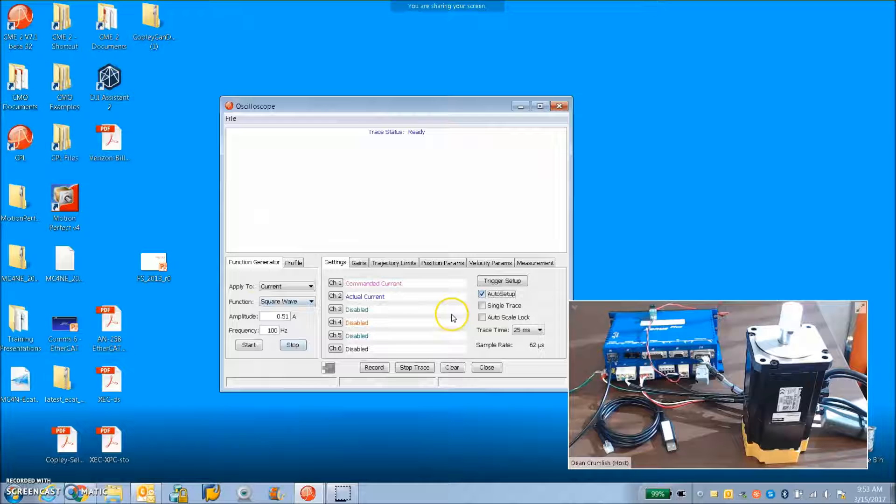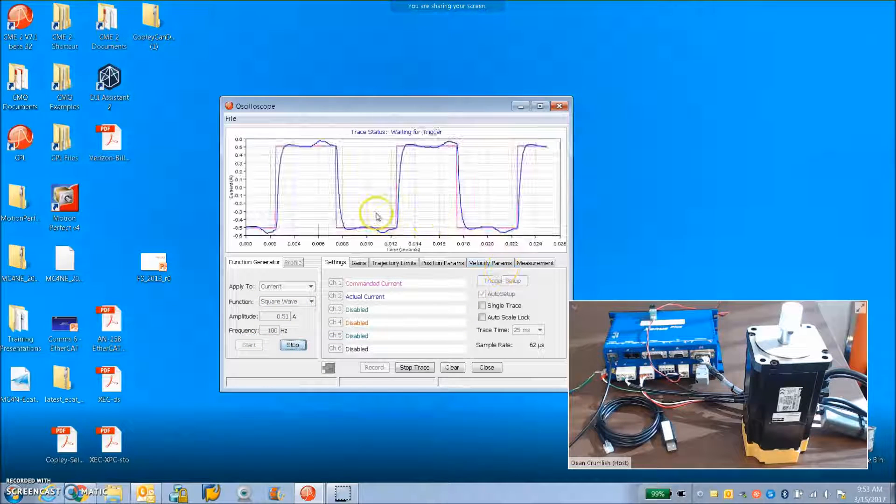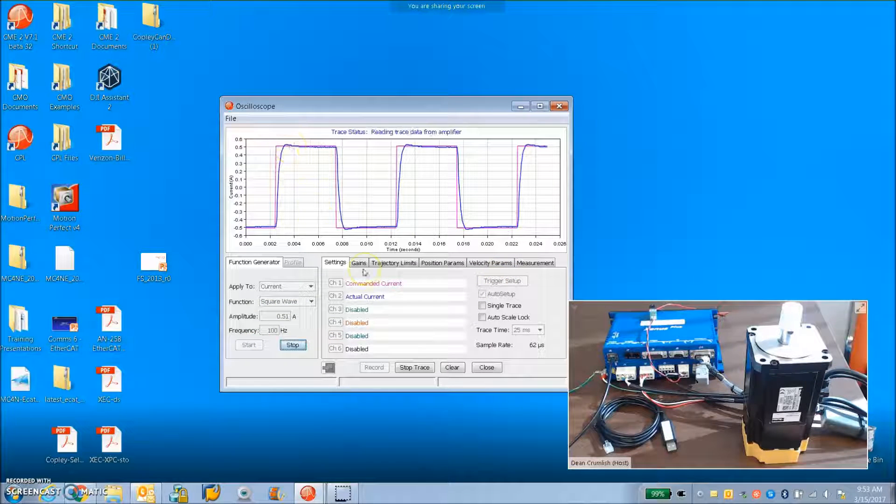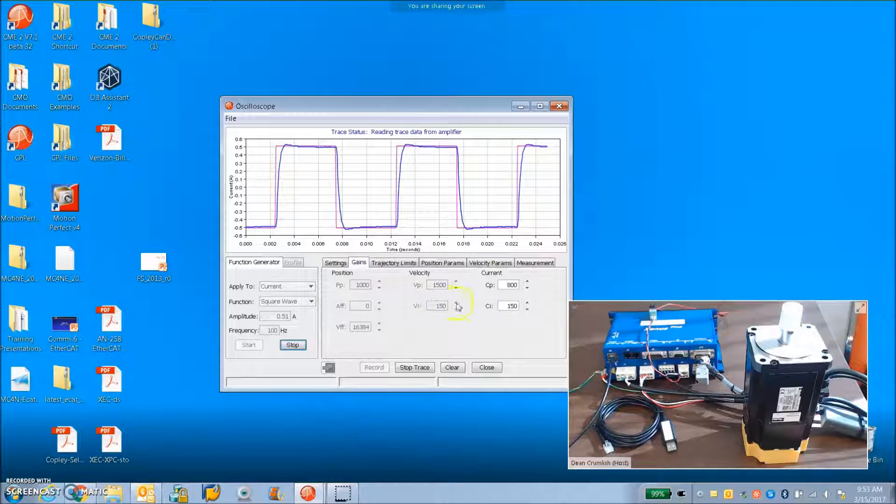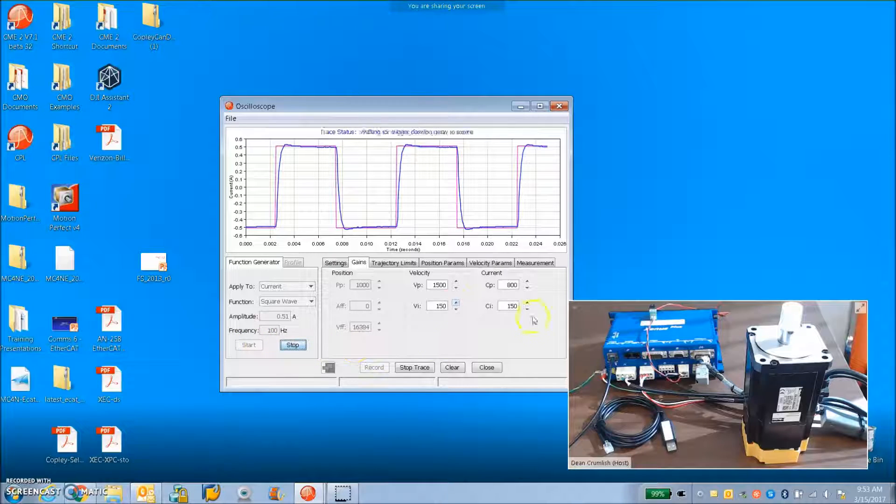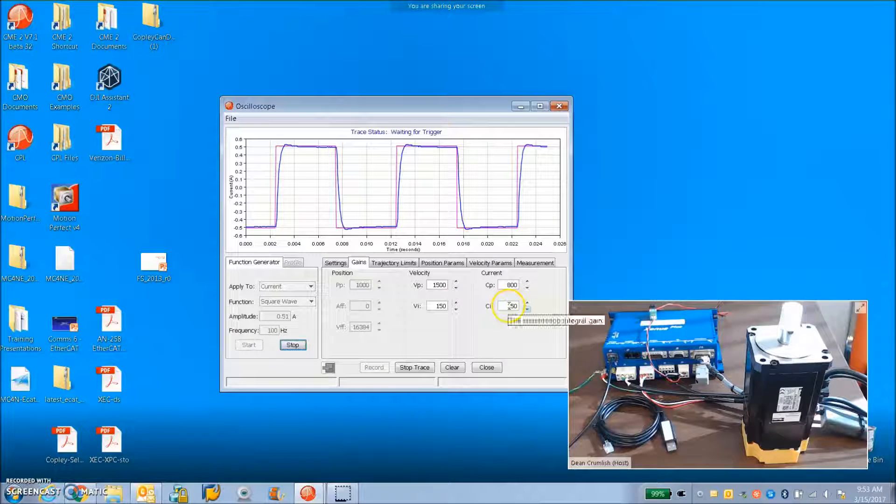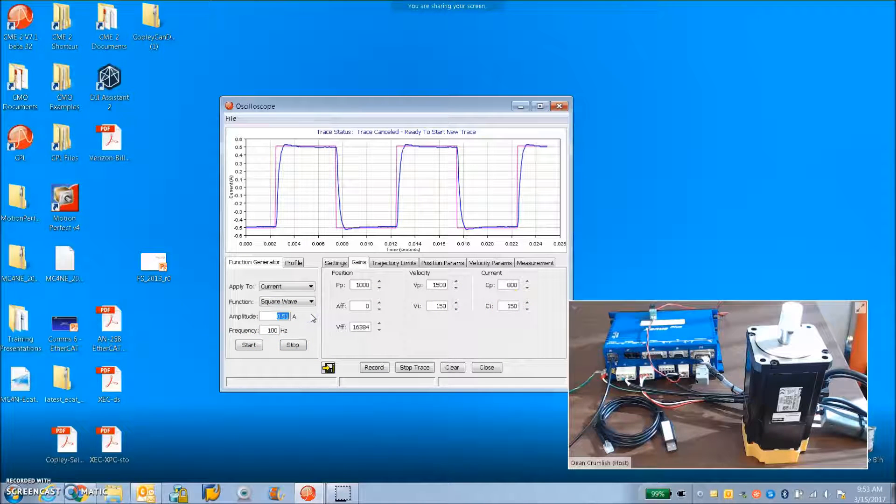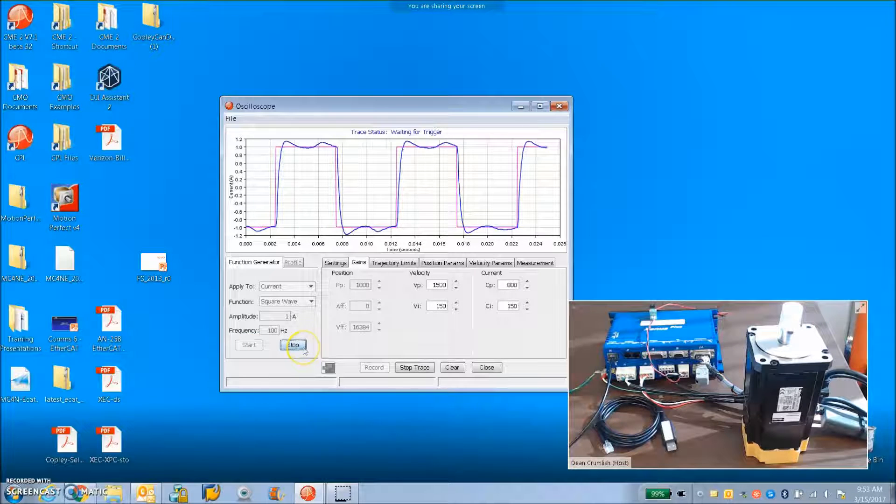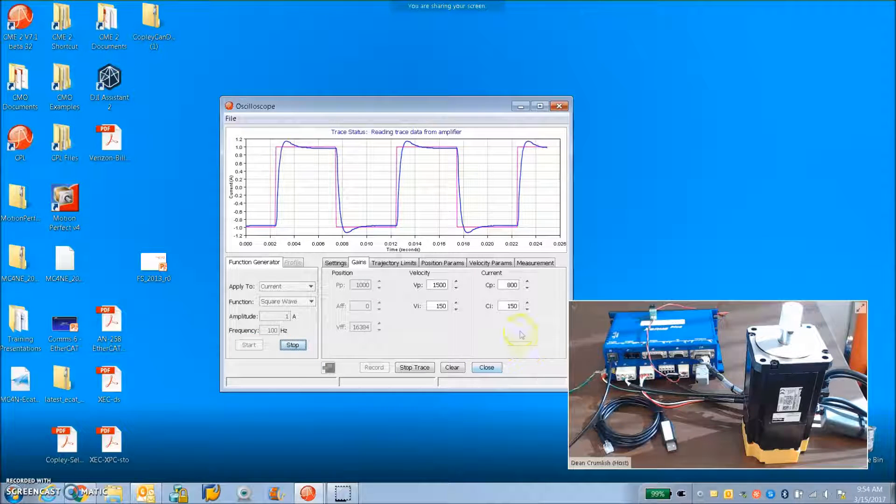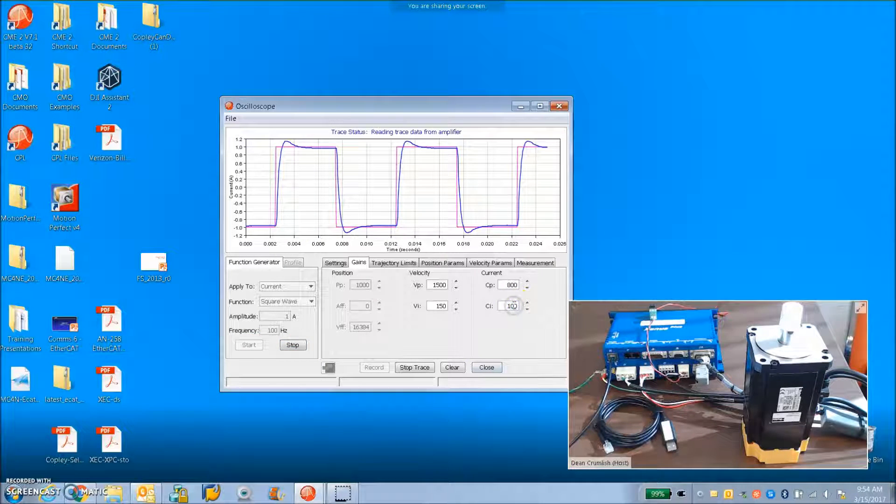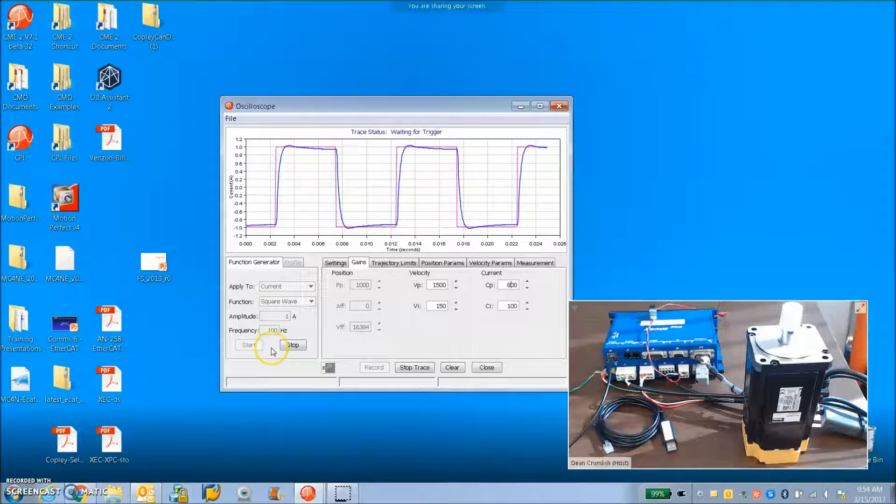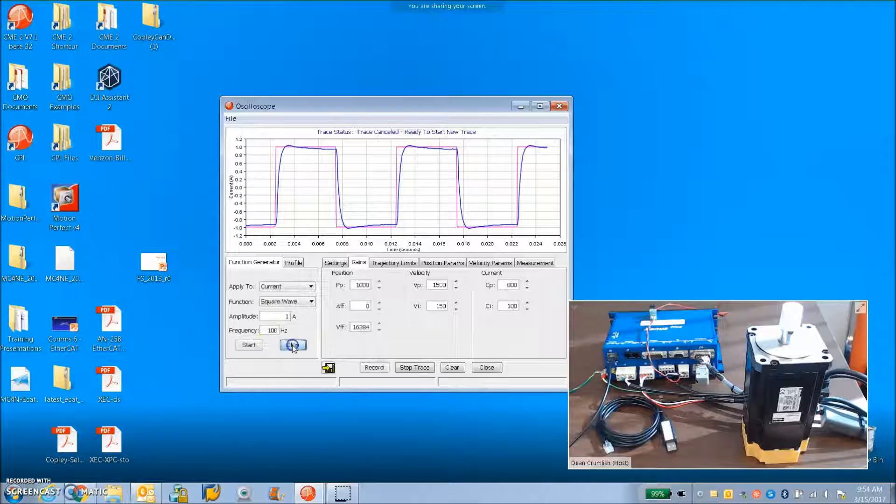Current, apply to the current loop, hit start. You can see a little bit of overshoot there. I could turn the integral down a little bit, but I like the bandwidth I was getting out of it. Not bad. A little bit more overshoot with the integral there. So let's knock a little bit off of that for high current.